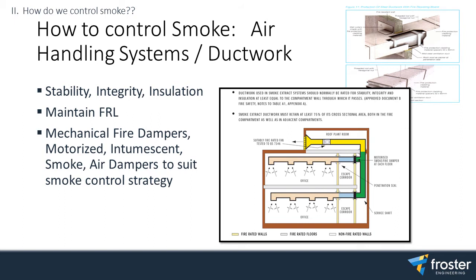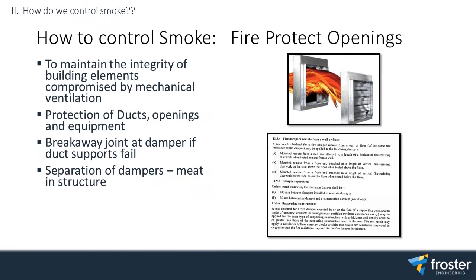Be familiar with the different types of dampers. You can have motorized control dampers, which form a smoke control strategy. Intumescent, we know once they close up from high temperature, that's it. They're isolated and they have to be removed and replaced. All right, the next section, fire protection of openings, to maintain integrity between fire zones.